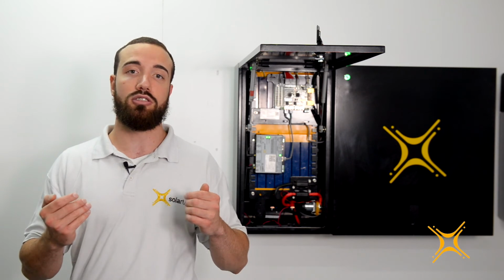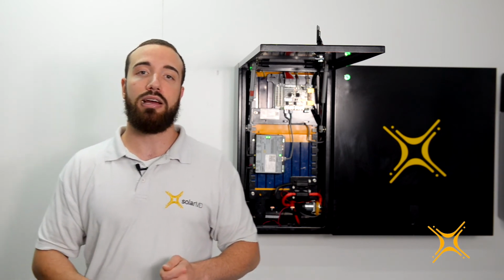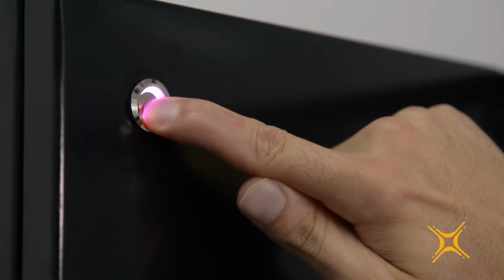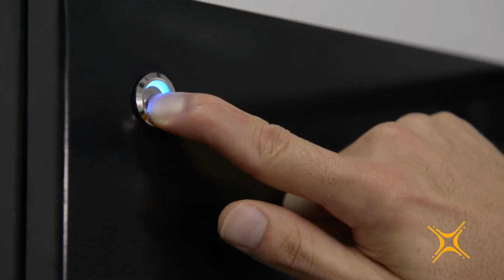If the LED is fading into the unit, it indicates charging, and if it is fading out of the unit, it indicates discharging. If the battery is in warning mode, the multi-function LED will flash orange every second and take priority over the capacity and current flow direction. If the battery is in error mode, the button LED will flash red every second and take priority over the capacity and warnings. The multi-function button can also execute a predefined list of functions.